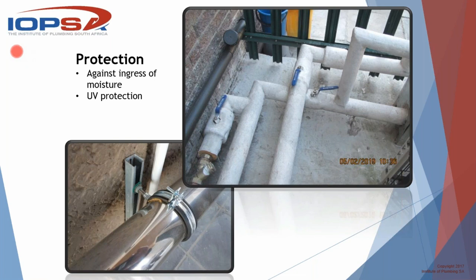Okay. Now, once you've put the lagging on, and if it's outside, you need to protect it. You need to protect it against two things: ingress of moisture, i.e. rain or whatever the case may be, and UV. UV rays have a hell of a negative effect on most things, and lagging's no exception. It'll destroy certain types of lagging within a few years, and then it's just gone. Then it's as if you've never had lagging there. So you've got to protect it.